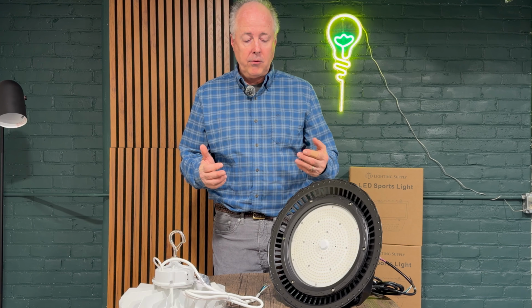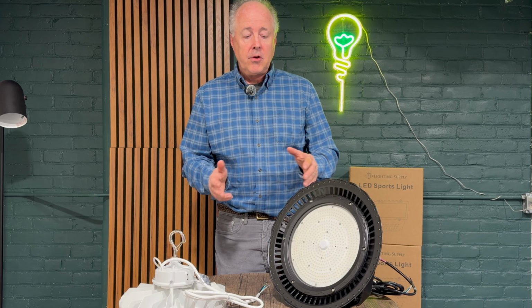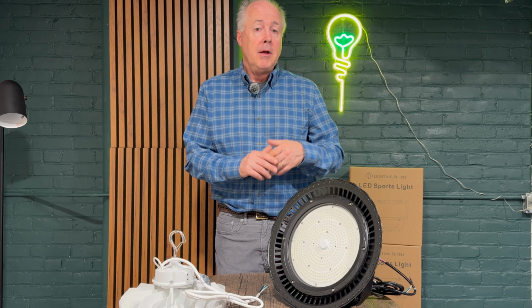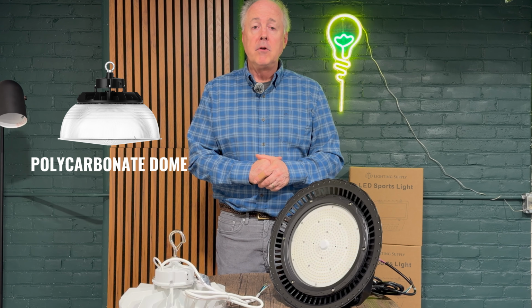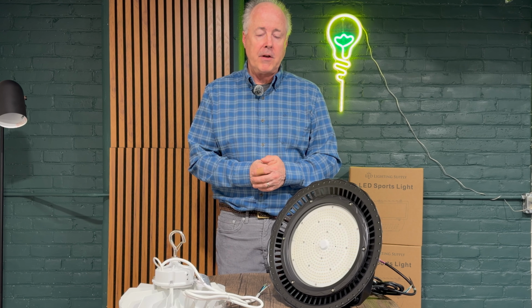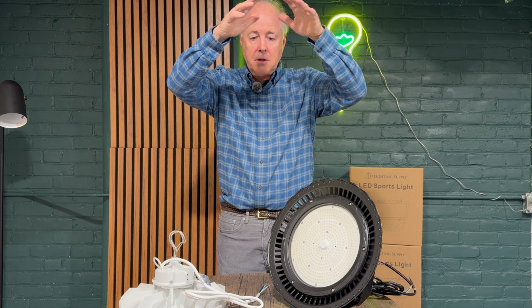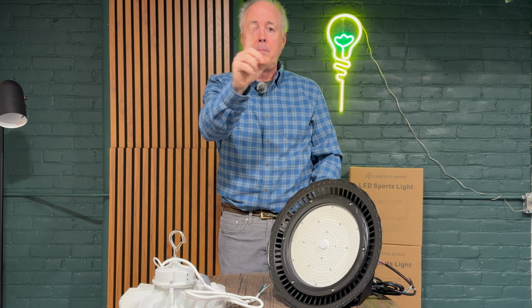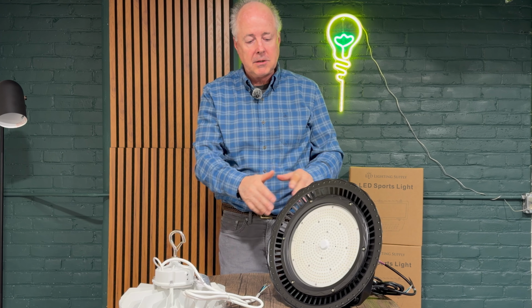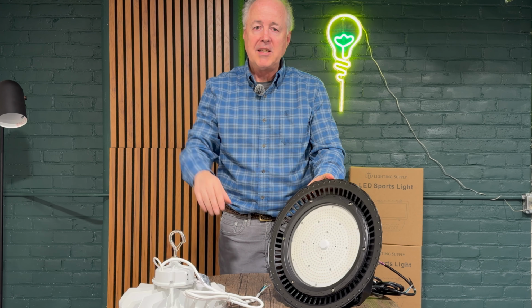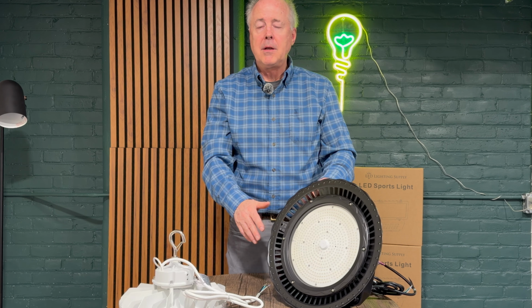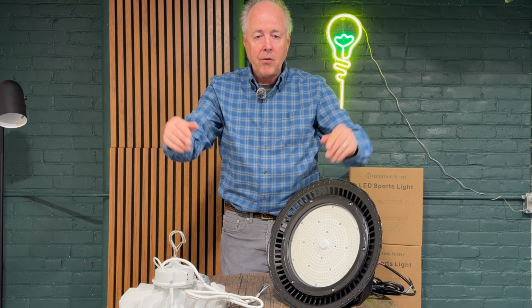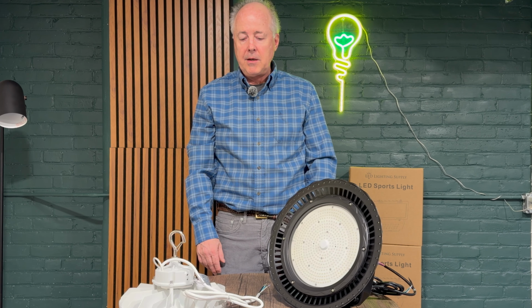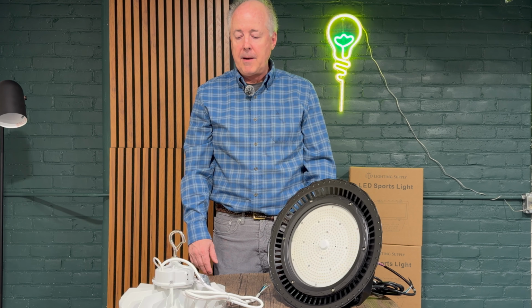Today, UFO high bays for LED don't have domes in most cases. They're available, but they aren't needed, versus an HID metal halide fixture, which needed a dome because the dome shined the light down, since you had a bulb shining 360 degrees. With LEDs, the light all shines down, and usually there's an optic directing the light. So a dome's not needed, but if you want one, you can get it.